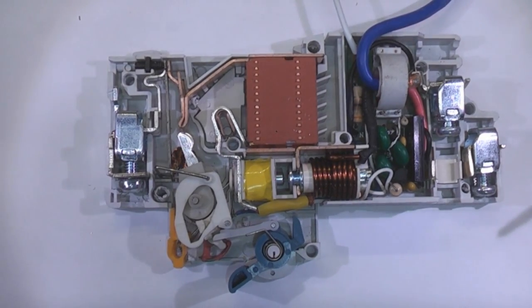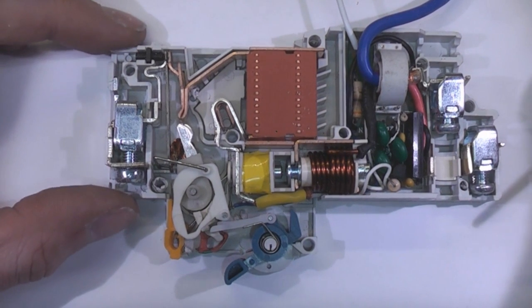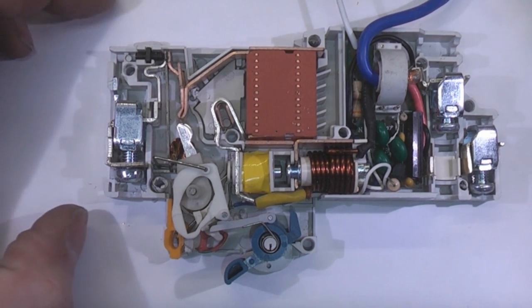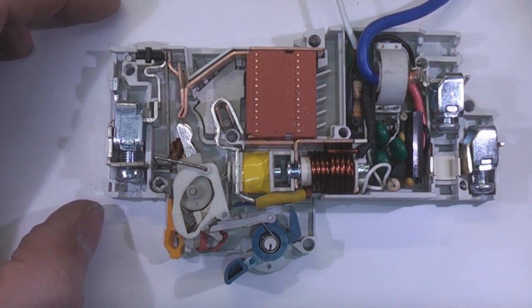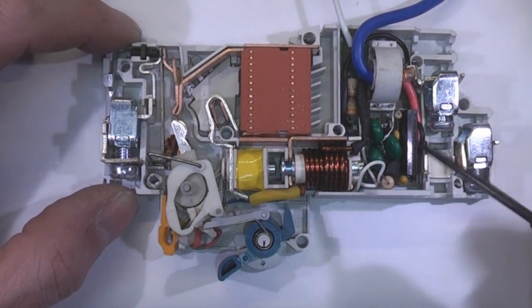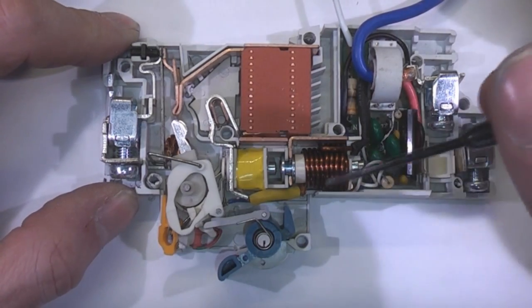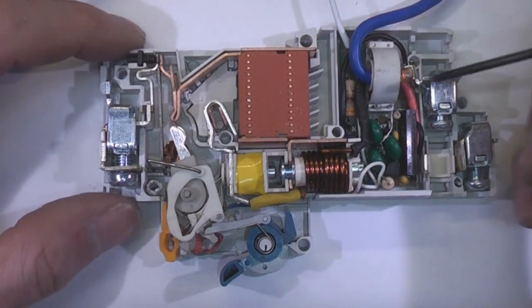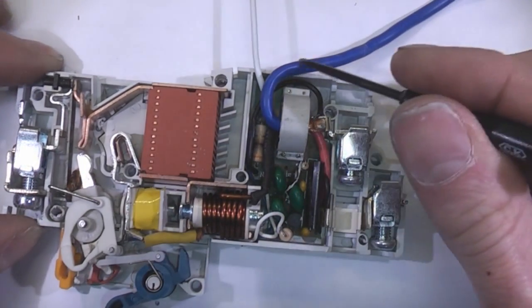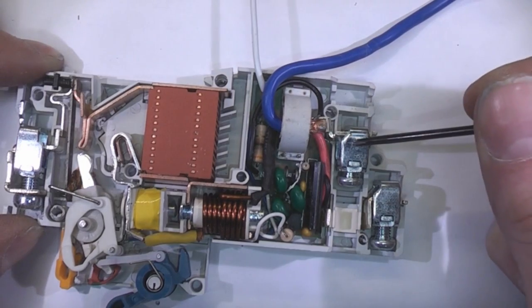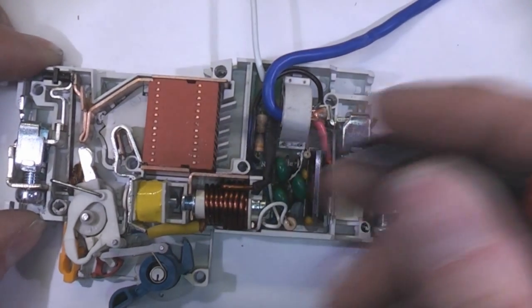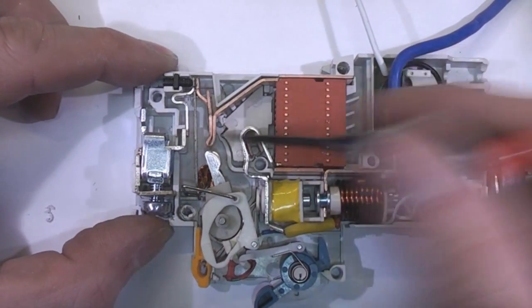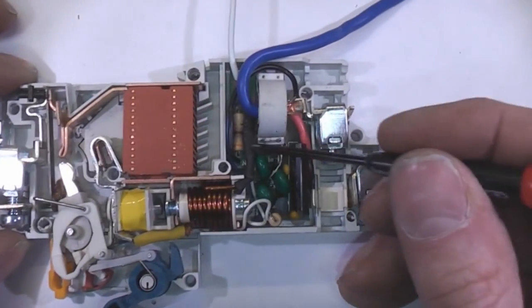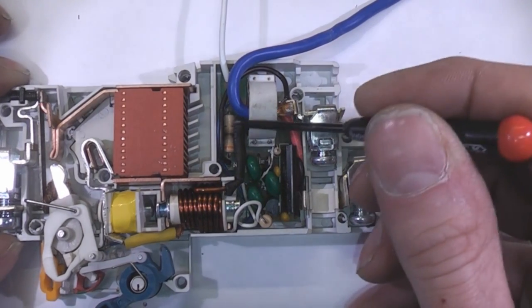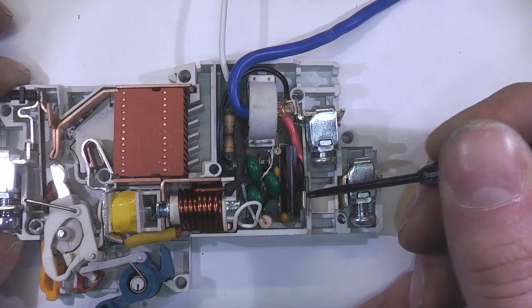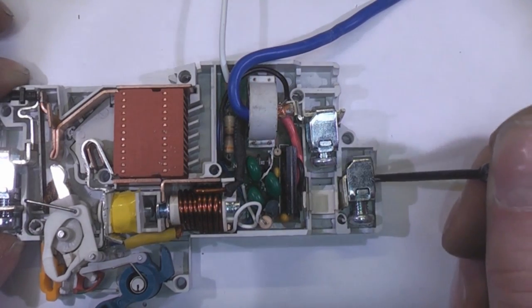Right, now when we open this up, there's actually quite a surprising amount of stuff in here. For something you think, oh, it's just a circuit breaker, it just trips when the current goes over, you might think it's quite simple, but actually there's quite a lot of subtle things going on here. Because the RCD and the overcurrent protection are effectively completely separate circuits, let's look at the RCD stuff first. We've got the neutral wire coming in, goes through the current transformer and then goes out on this terminal to the load. The live comes in. I'll deal with the overcurrent section in a minute, but basically the live ends up coming out here, again through the current transformer, and then to this tab which is connected to the live load terminal.